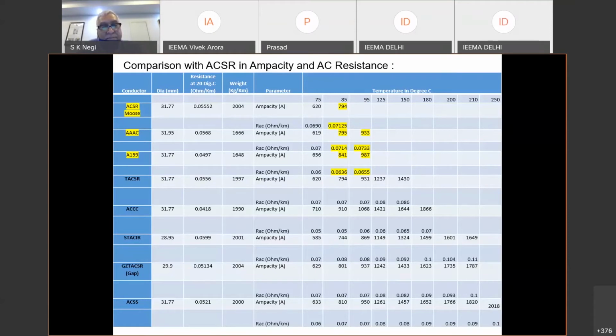So we have used it by using a 3-meter extension on an existing tower, or using a lesser span in a 400 kV line, and then doing the cost benefit analysis, the power flow which it will give ultimately in the next 5 to 10 years, and what the break-even point is and where it will be beneficial to the utility, taking into account the I-square R losses which are lesser here. So one has to do more of an application engineering, I will say.